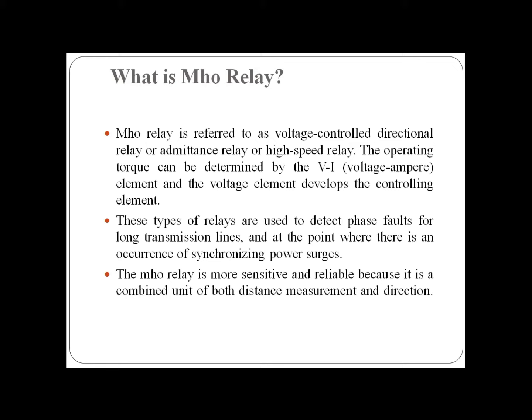These types of relays are used to detect phase faults for long transmission lines and at points where there is an occurrence of synchronizing power surges. The Mho relay is more sensitive and reliable because it is a combined unit of both distance measurement and direction.